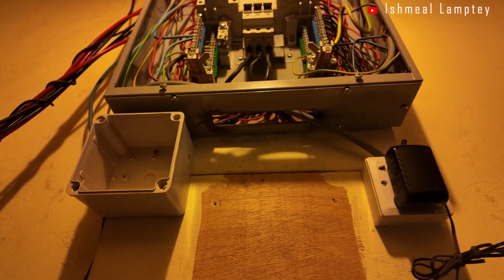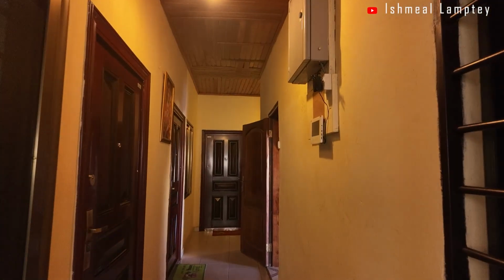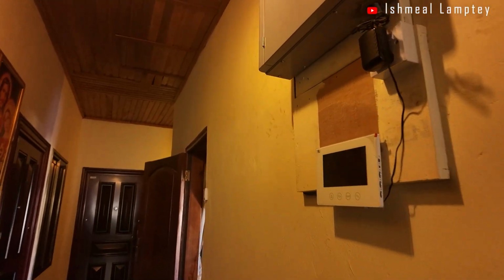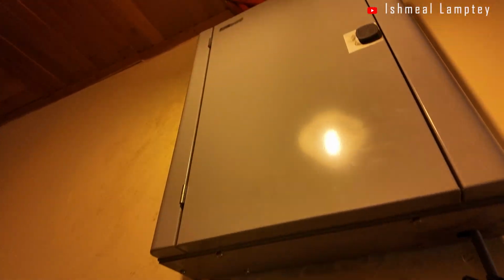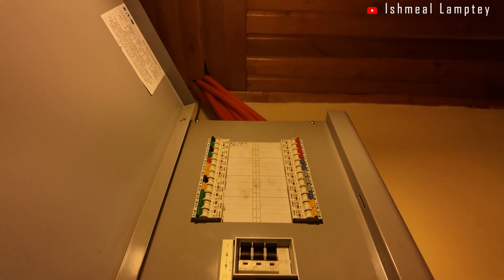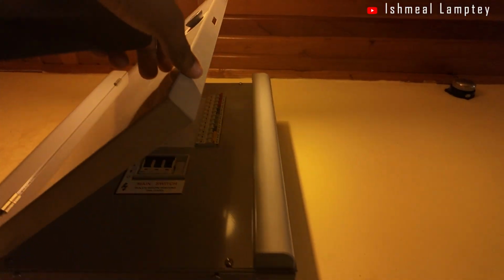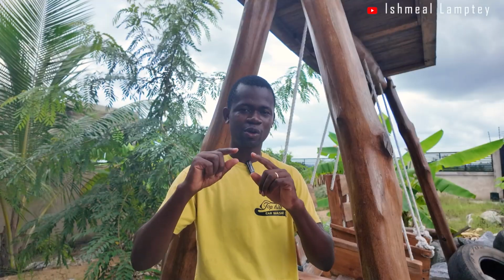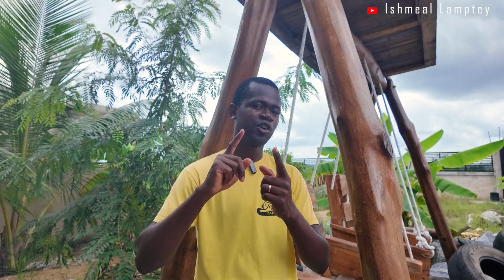Then we were able to identify one particular breaker, because we had to turn off everything, then turn on one after the other to see what was the problem. Then we realized that there was a particular breaker which was providing power to a specific room, now the socket of the room, and the configuration was done wrongly. Instead of the earth serving as the earth, the earth was connected to the live phase, and then the live was actually connected to the earth. So it was wrong, and it was powered on, so it was sending wrong feed or signal to the inverter, which was preventing that from functioning. So we had to trace that.